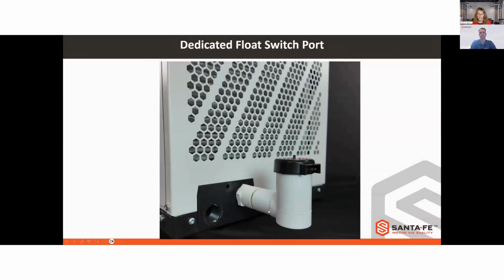We have incorporated a dedicated float switch port on these units. You'll see it right here above the drain port. You can install a float switch on this. And again, we talked about how this can wire directly to the terminal block, to those float terminals. And if for some reason that dehumidifier drain were to back up, it would automatically activate the float and shut off the dehumidifier.